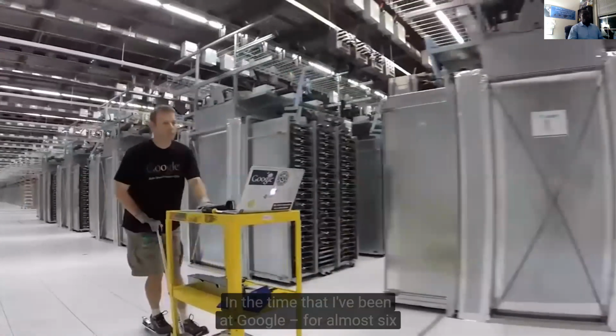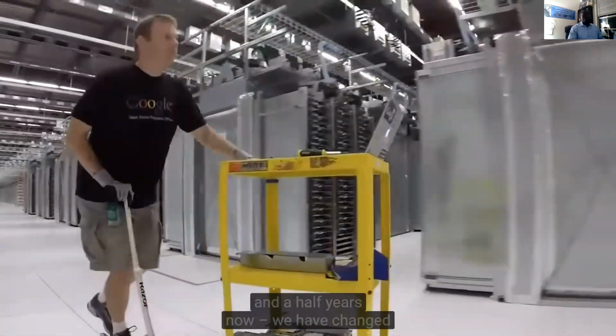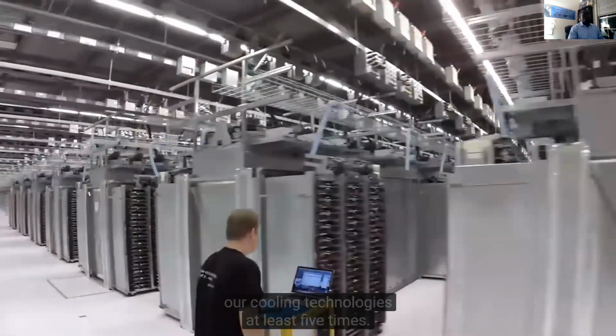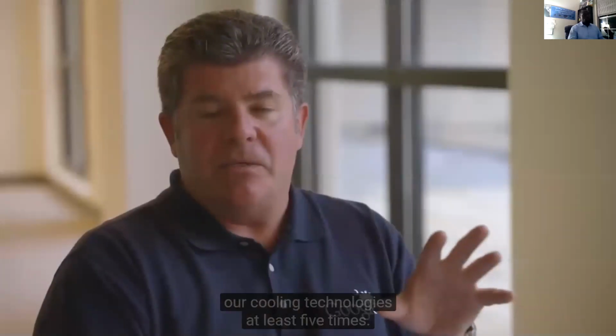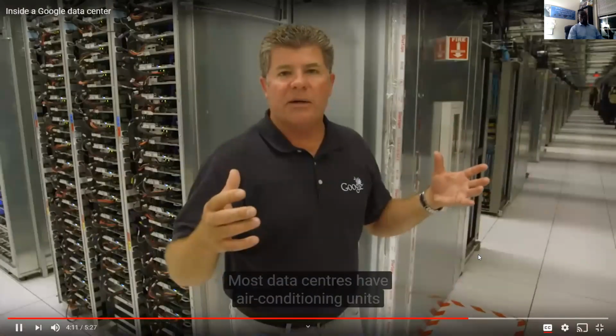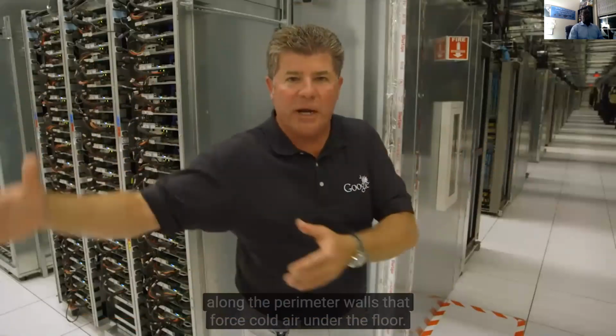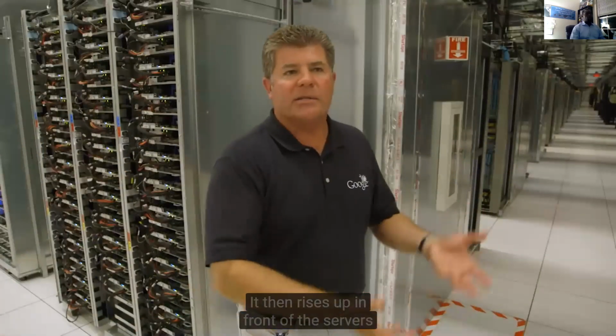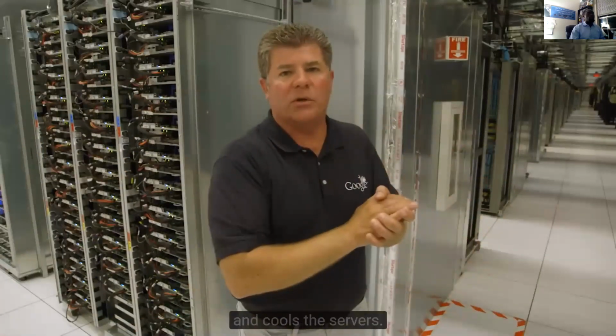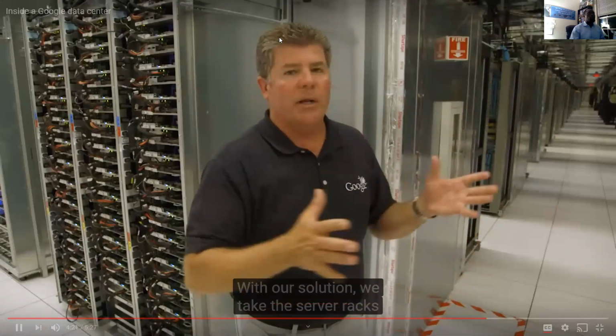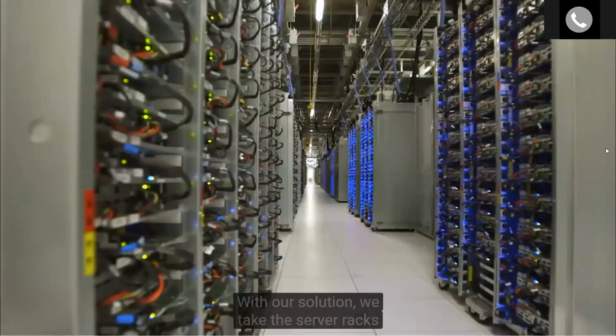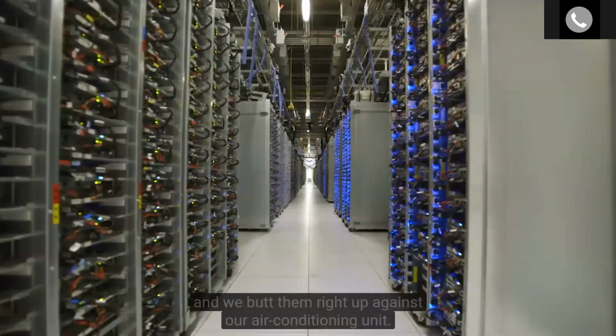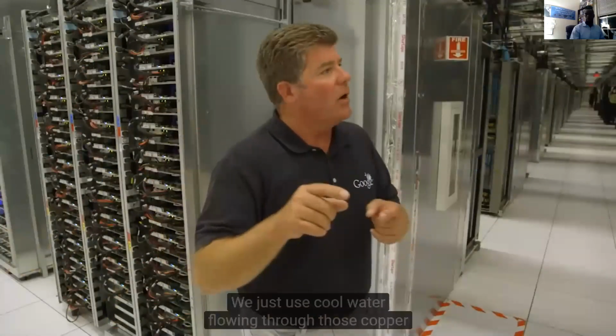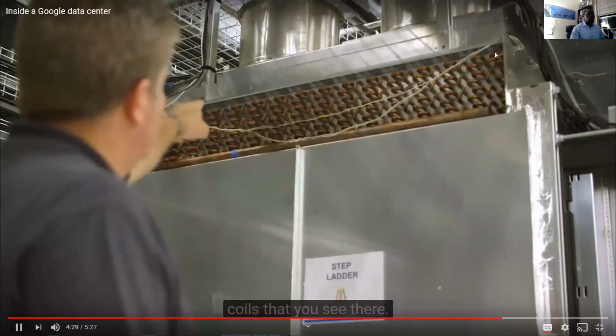In the time that I've been at Google, for almost 6.5 years now, we have changed our cooling technologies at least 5 times. Most data centers have air conditioning units along the perimeter walls that force cold air under the floor that then rises up in front of the servers and cools the servers. In our solution, we take the server racks and we butt them right up against our air conditioning unit. We just use cool water flowing through those copper coils that you see there.